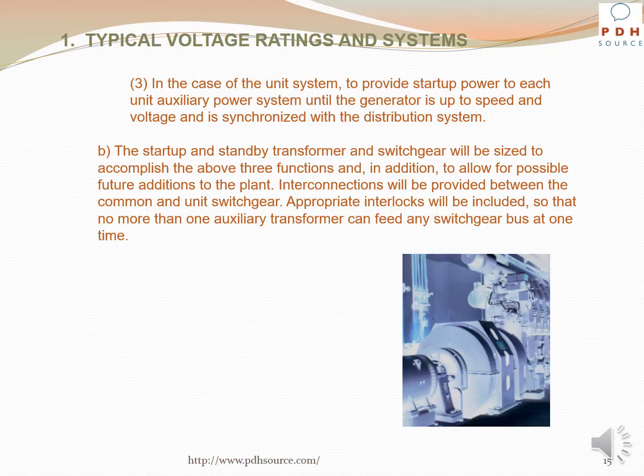The startup and standby transformer and switchgear will be sized to accomplish the above three functions, and in addition to allow for possible future additions to the plant. Interconnections will be provided between the common and unit switchgear. Appropriate interlocks will be included so that no more than one auxiliary transformer can feed any switchgear bus at one time.